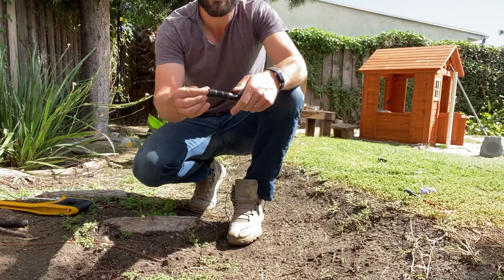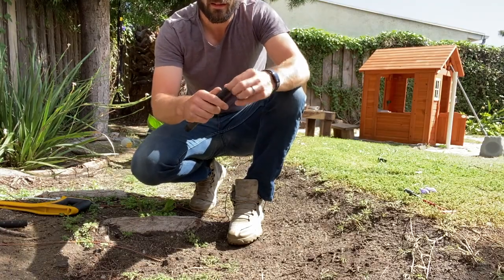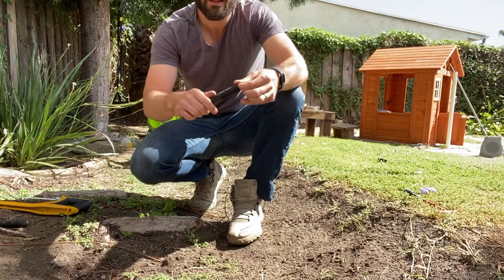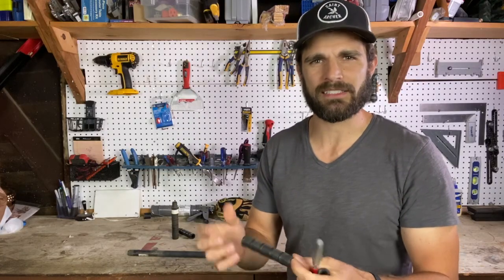The one thing I would suggest is to make sure that you sand or shave off any burrs that are on the riser once you've cut it. Because if you leave any of those on there, it will cause things to catch or build up inside of your sprinkler system and will cause errors down the road.